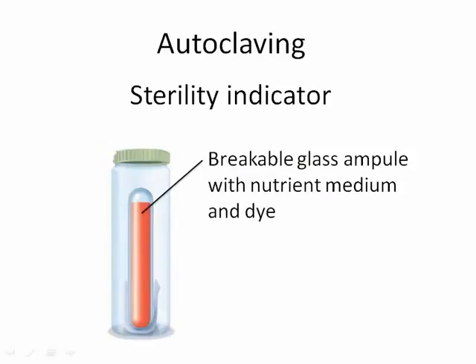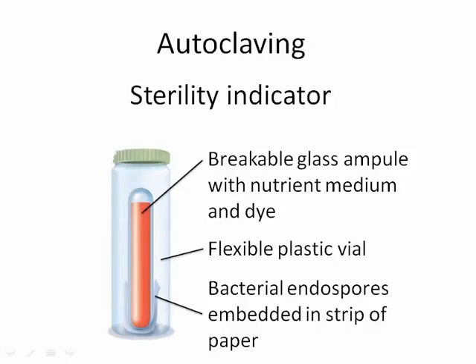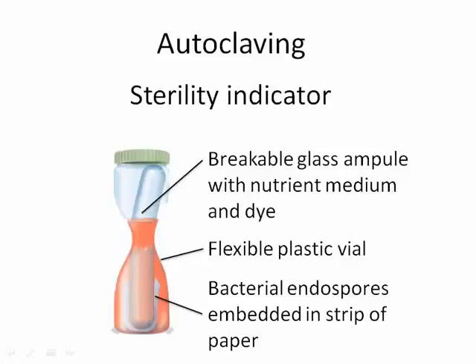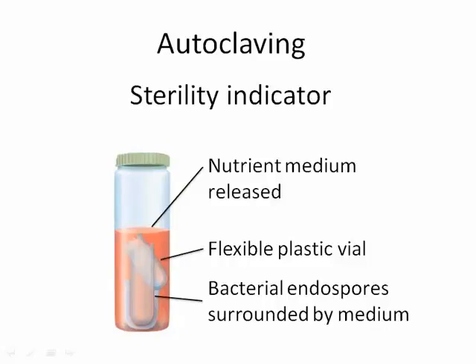A more accurate but also more costly sterility indicator is a breakable glass ampule that contains nutrient medium and an indicator dye. The ampule is inside a flexible plastic vial along with some hard-to-kill bacterial endospores. The vial's lid is porous to steam. After autoclaving, an operator squeezes the plastic vial to crush the glass ampule, which releases the nutrient medium into the vial with the endospores. After the vial is incubated for an appropriate time, it is examined.